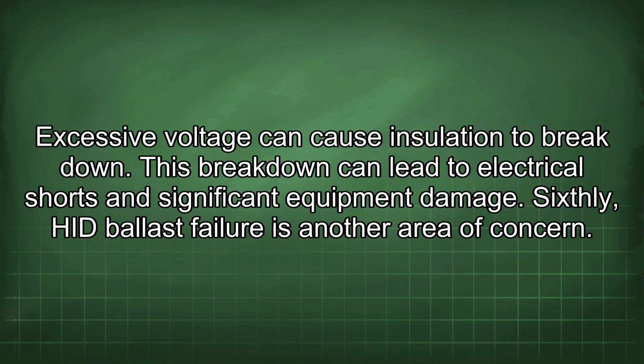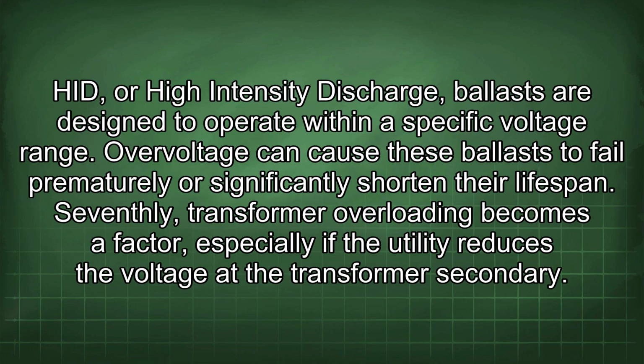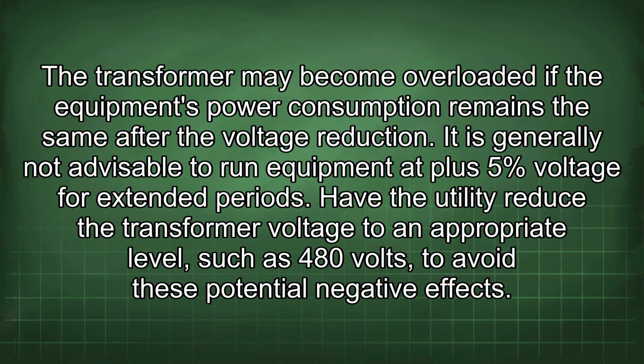Sixthly, HID ballast failure is another area of concern. HID, or high-intensity discharge, ballasts are designed to operate within a specific voltage range. Overvoltage can cause these ballasts to fail prematurely or significantly shorten their lifespan. Seventhly, transformer overloading becomes a factor, especially if the utility reduces the voltage of the transformer secondary. The transformer may become overloaded if the equipment's power consumption remains the same after the voltage reduction.